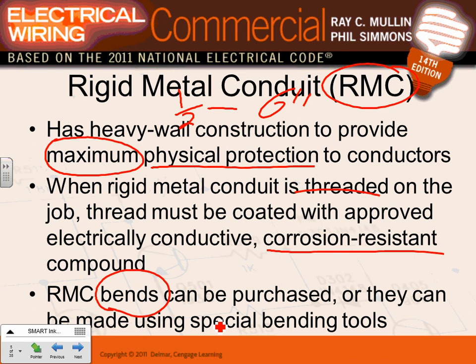They come in different materials: steel, aluminum, brass. For highly corrosive environments, brass is a good application. Where would you use rigid metal conduit? Bringing service above ground into the building, manufacturing floors where cranes are running, heavy industrial applications, hazardous locations - class one, class two - gas stations, chemical plants, and above-ground service.